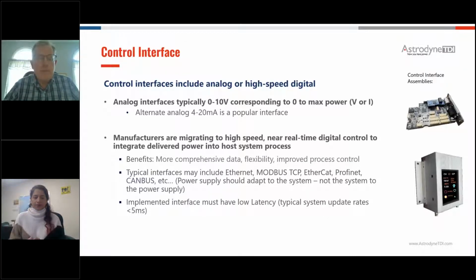What we're finding in newer applications, though, is that applications are migrating to a serial digital bus for control. This gives much more power with regard to comprehensive data availability and flexibility, which ultimately can lead to improved process control. You'll see digital buses such as Ethernet or Modbus TCP, EtherCAT, CAN bus, or others. Every customer or every application that we see has its own personality with regard to the type of interface they try to use. One thing that is common, though, is that these applications are looking for very low latency, very fast response time, less than 5 milliseconds. More often than not, we're seeing less than 1 millisecond these days, such that the power supply can be a near real-time component of a control loop, so that the control loop can maintain proper control of the process in a very quick manner.